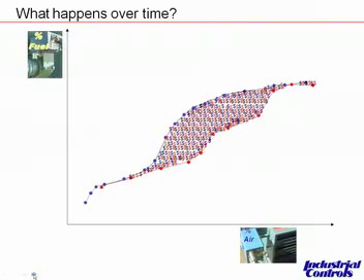Now fuel's on the left and air is on the bottom. The blue curve is ultimately where we want it to be, but understanding that with time there's going to be slop and changes in the combustion equation, the person will leave some excess air in there. The difference between the optimum and where it's going to end up or where it's set up is opportunity for dollar savings in the form of reduced fuel consumption.